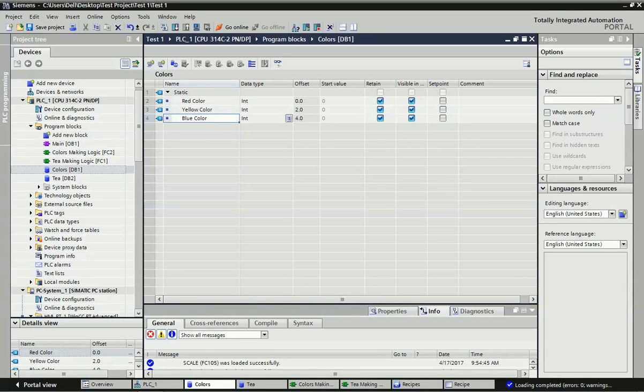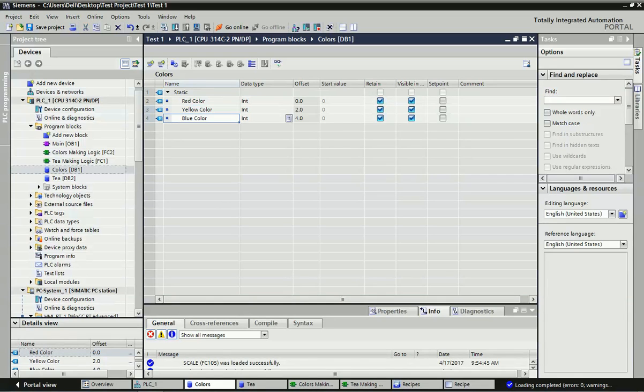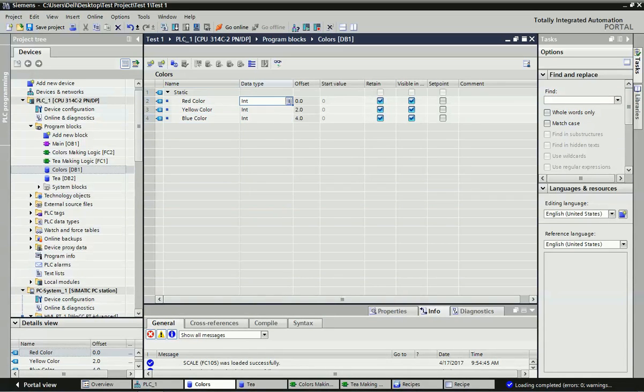After adding the data block, you have to add the elements for the recipe. If you are talking about color, there are mainly three colors available: red, yellow, and blue. From these three colors we can make multiple colors as per our application or demand. I have taken three types of elements. You just click this button to add the element. The data type I will take is integer, because the value we are entering from the recipe or SCADA is in integer. Always remember: this recipe data type should be integer.